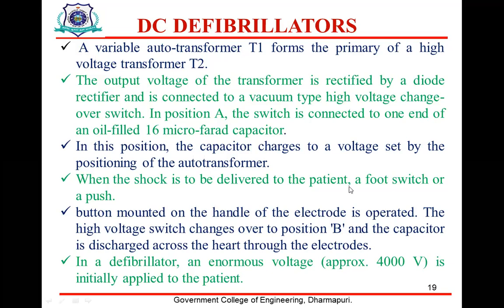When the shock is to be delivered to the patient, the foot switch or a push button mounted on the handle of the electrode is operated. The high voltage switch changes over to position B, and the capacitor is discharged across the heart through the electrodes. In a defibrillator, an enormous voltage, approximately 4,000 volts, is initially applied to the patient.